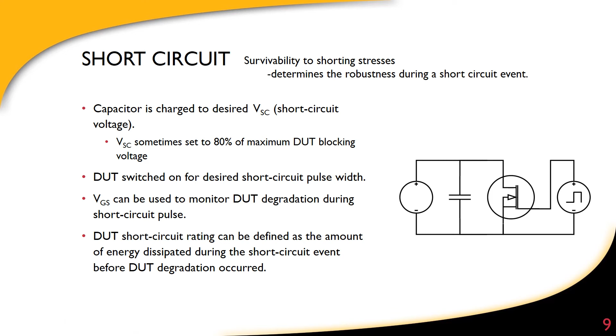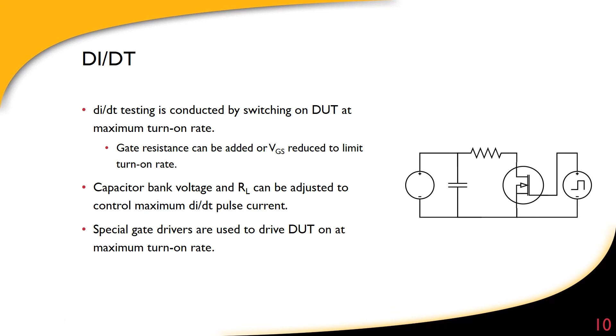For the DIDT test, it's conducted by switching the DUT on as fast as possible. We can change that switch-on rate by changing the gate resistance. The capacitor bank voltage and the resistor can be adjusted to control the maximum pulse current. Special gate drivers are used for this test to drive the DUT and get the physics as close as possible to achieve that very fast turn-on time.